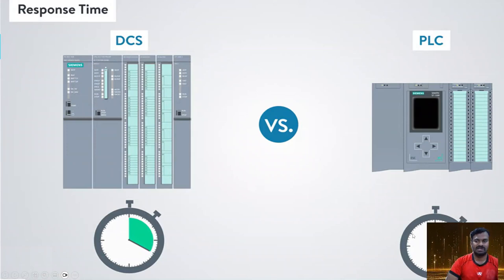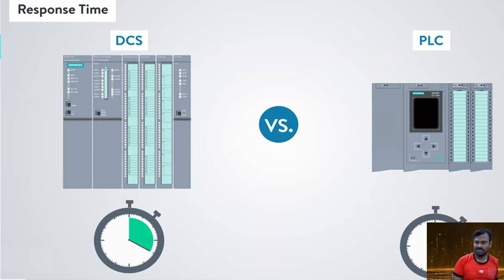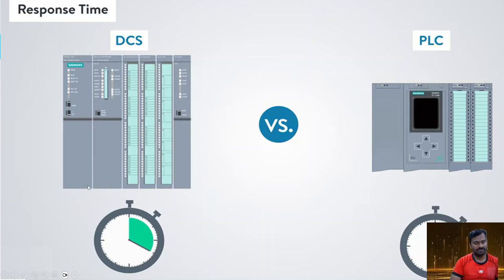Regarding response times, PLC is faster than DCS. Because PLCs handle fewer inputs and outputs and simpler programs, the input scan, program scan, and output scan are completed faster. DCS has more complex loops and processes, and more inputs and outputs to execute each cycle, making DCS somewhat slower than PLC.